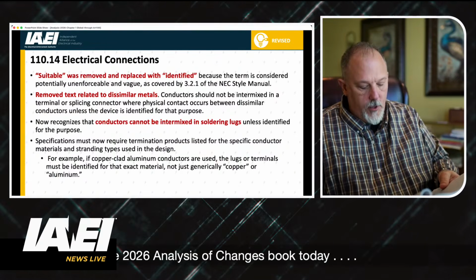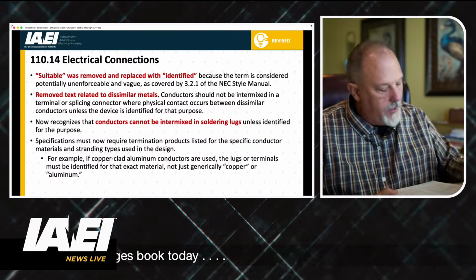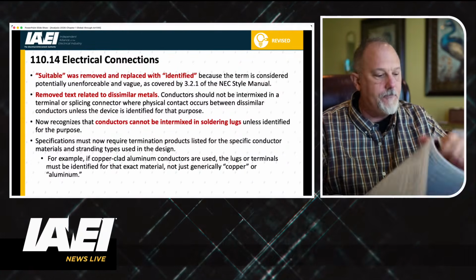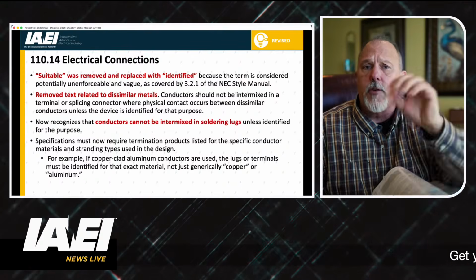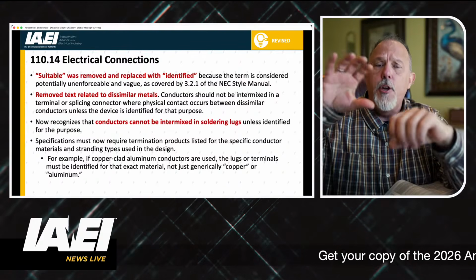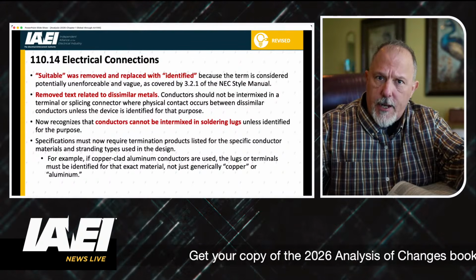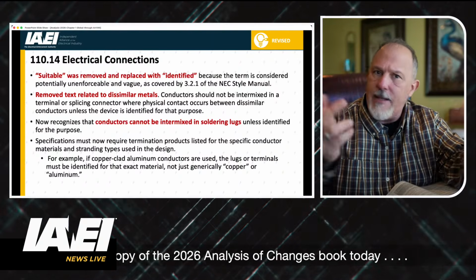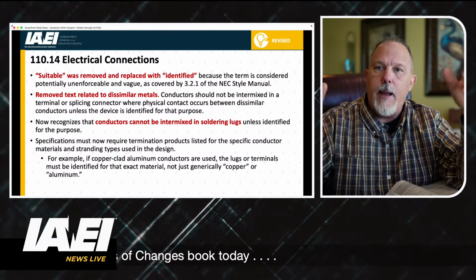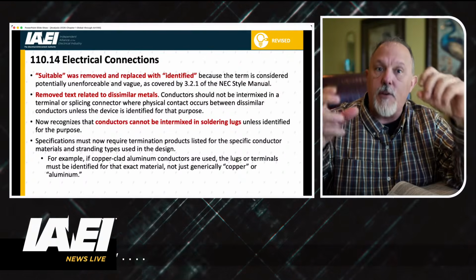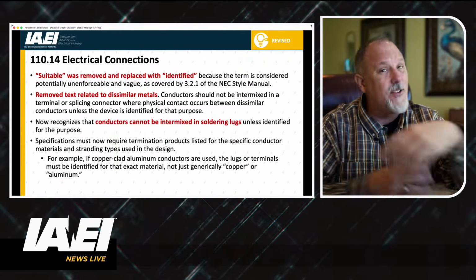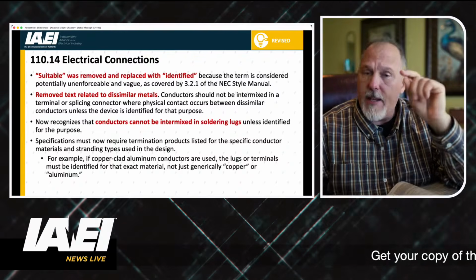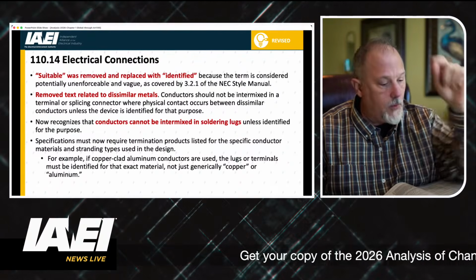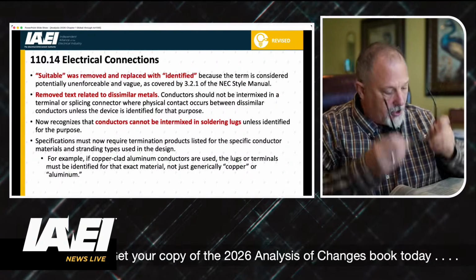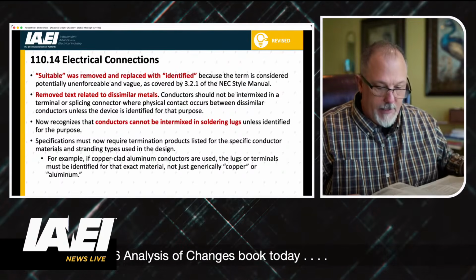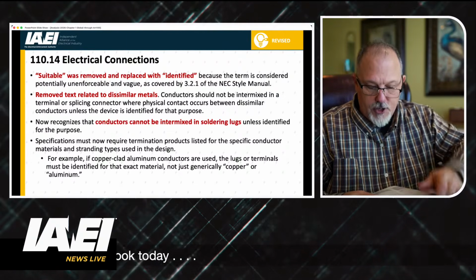110.14, what do we use 110.14 for, Willie? What we do is we focus on 110.14 for terminations. And remember, in the overall circuit, I worry about the conductor ampacity. That's a chapter 3 thing. But the termination and the amount of current I'm permitted to take through a termination, that's a 110.14 thing. But there's even more in 110.14 than just the temperature, because you got A and B that you got to think about. So A is your terminals.